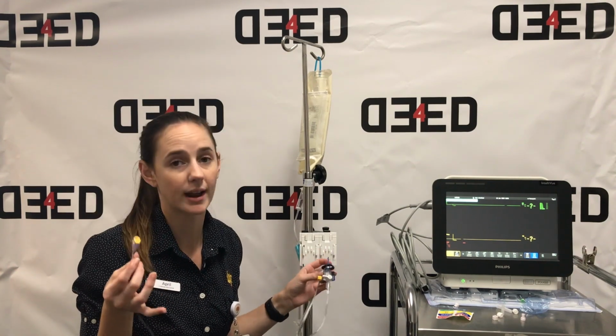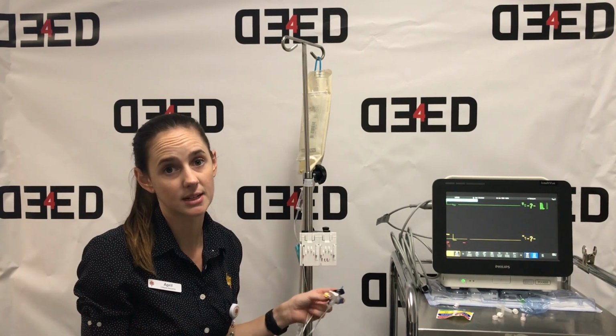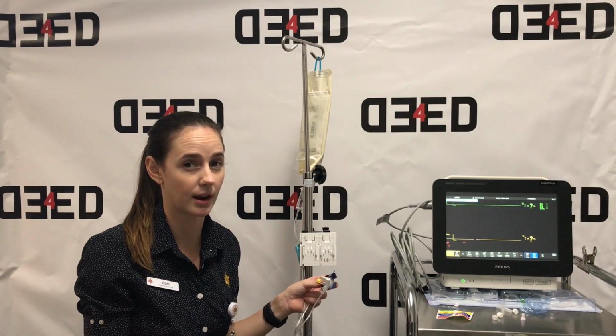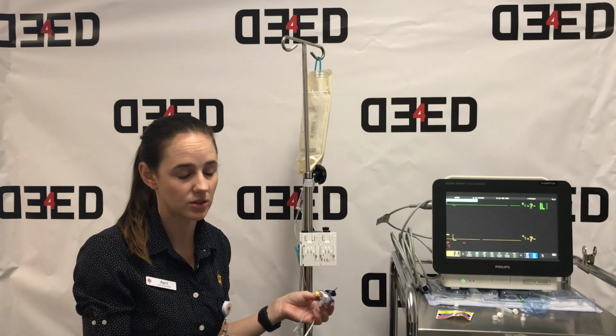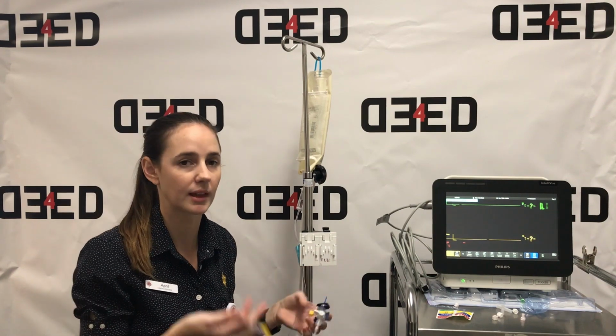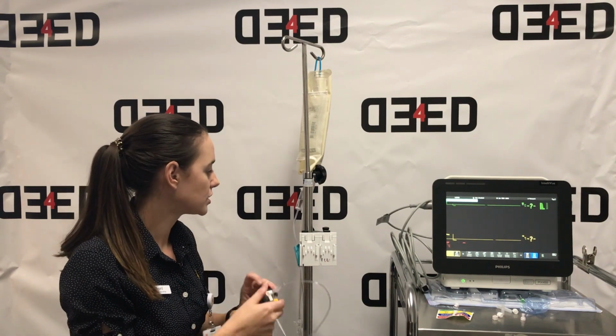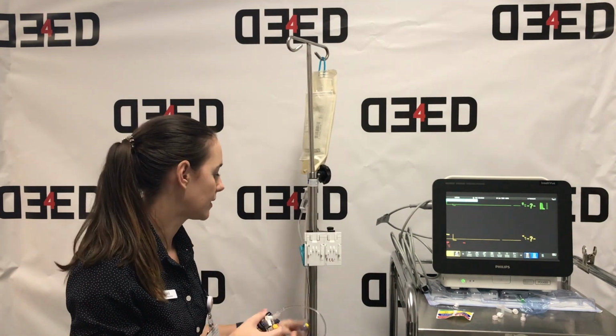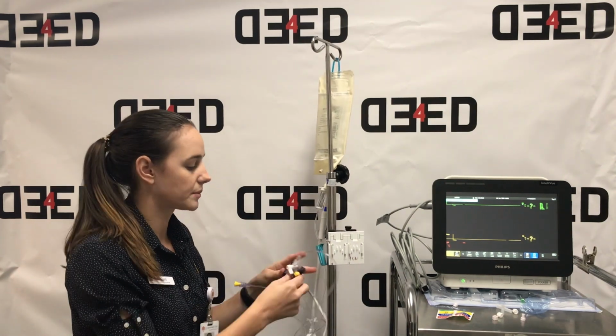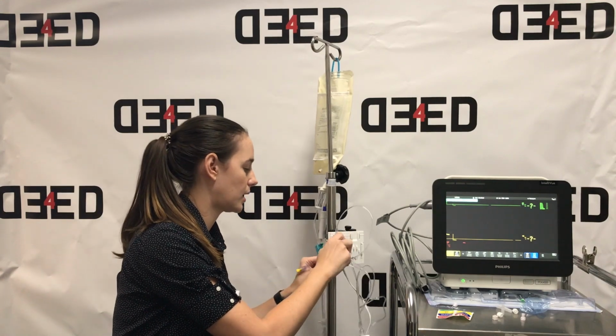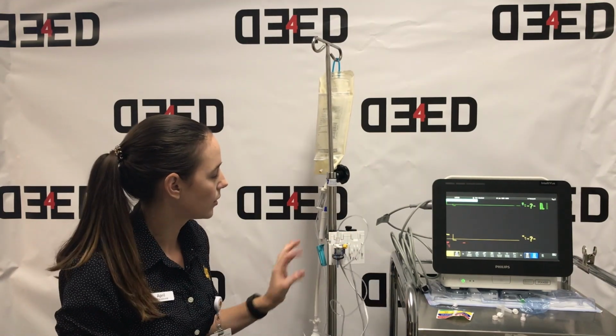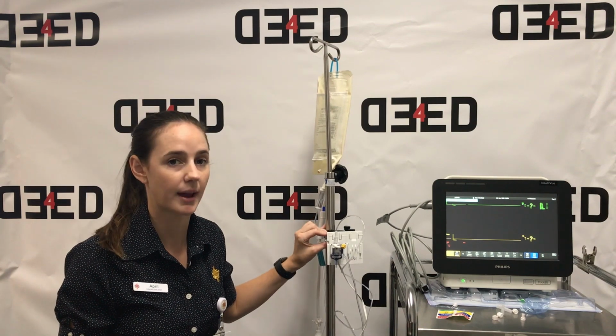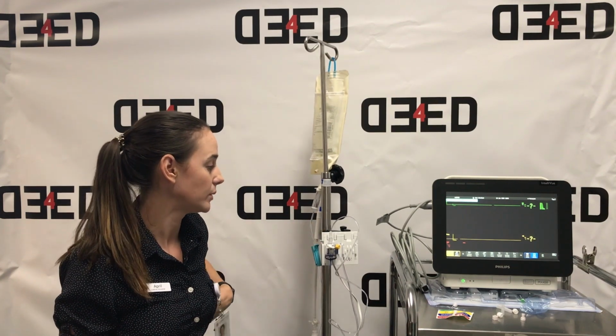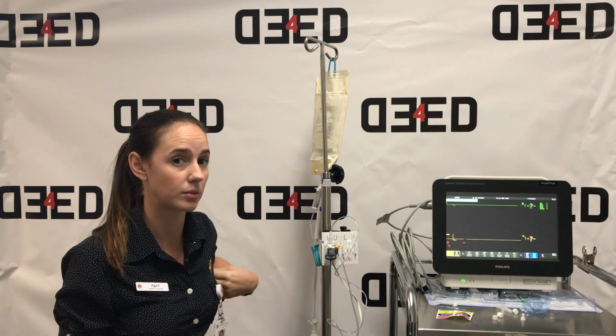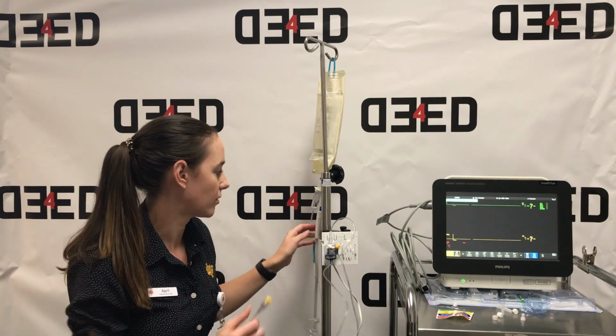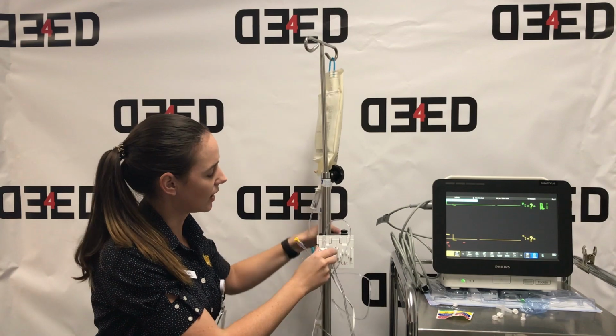So that is now primed and ready to be connected to the patient. It's not ready to give you an actual reading yet, but in any event, this is probably the most important part that you need to get ready for the doctor to connect once they've inserted the line. The rest, when it comes to zeroing things, you can do after. So grab your IV mount, pop that on the patient's IV pole, and pop your little connection into the mount there. And then just level this with the patient's phlebostatic axis, which is the fourth intercostal space on your mid-axillary line. It lines up with the right atrium. So just make sure that's at the right level.